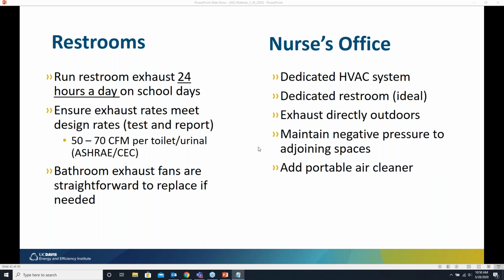Also, there are recommendations for a nurse's office or where sick children wait to be picked up. It should have a dedicated HVAC system so that you're not circulating that air to other spaces. Ideally, it should have its own restroom. That restroom exhaust should exhaust directly outdoors, and you should try and maintain a negative pressure to your adjoining spaces. If you're investing in portable air cleaners, the nurse's office would be a really high priority place to put one.